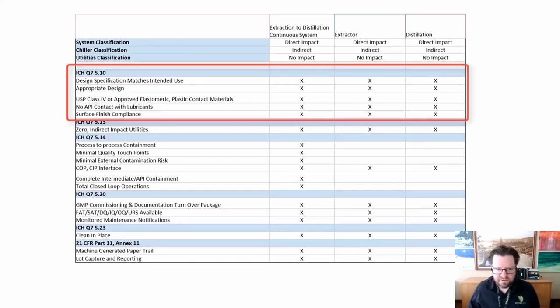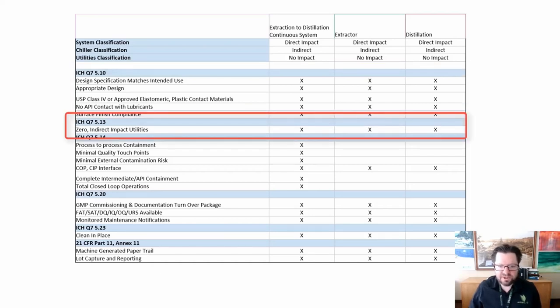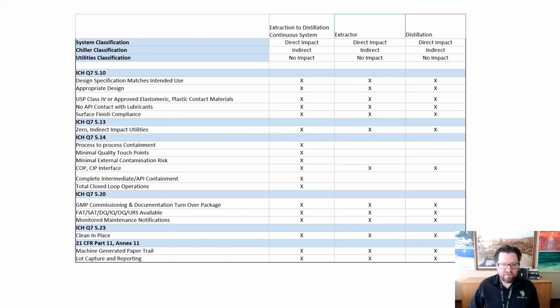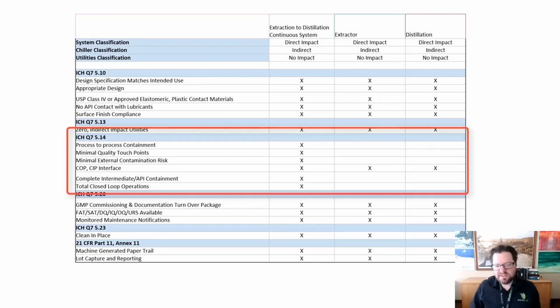This is ICH 5.10 — design specification matches intended use, appropriate design with USP Class 4. This has to do with internal contamination or lack thereof: no API contact with lubricants and surface finish compliance — all things related to cleanability and internal contamination. Our equipment really matches all of that. Zero or indirect impact utilities is the second thing for 5.13. And then in 5.14 we start to talk about containment and process containment, minimal quality touchpoints, minimal external contamination risk, clean-out-of-place, clean-in-place interfaces, and total closed operations — this is really where that continuous extraction-to-distillation system really shines.